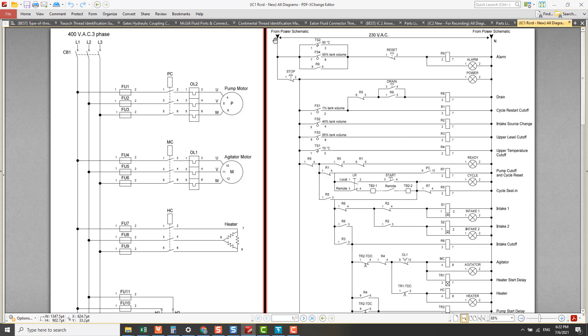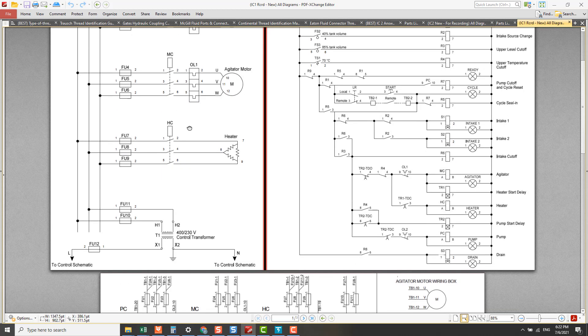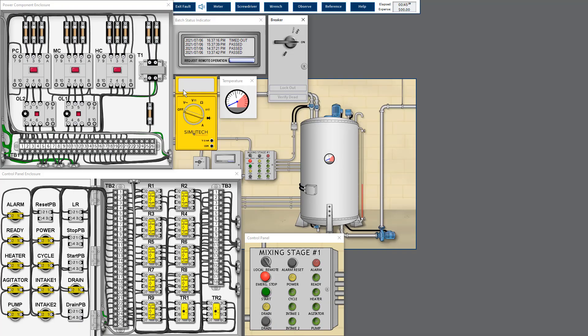The AC current is from the power schematic. Current from the transformer flows to the control schematic via the fuse. If the fuse is blown, there's no way the current can flow to the control schematic, so we have to measure the fuse.